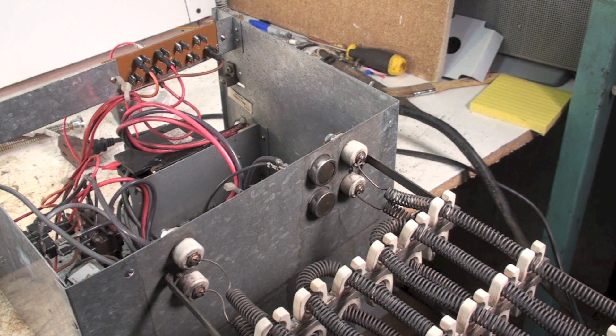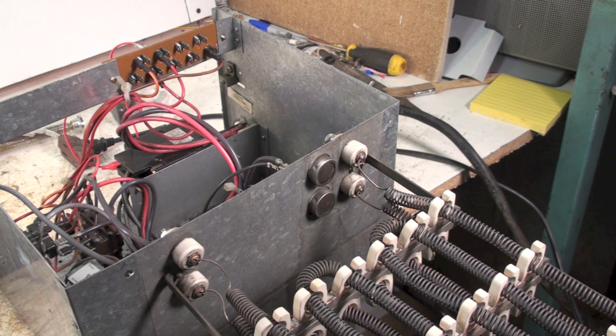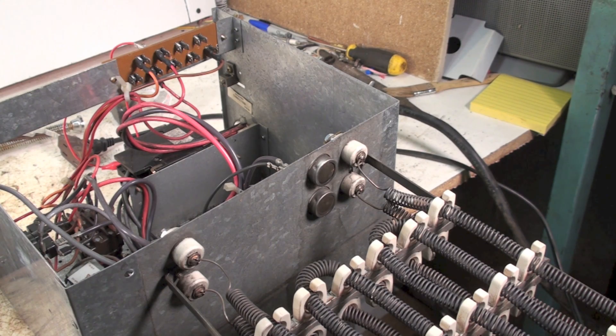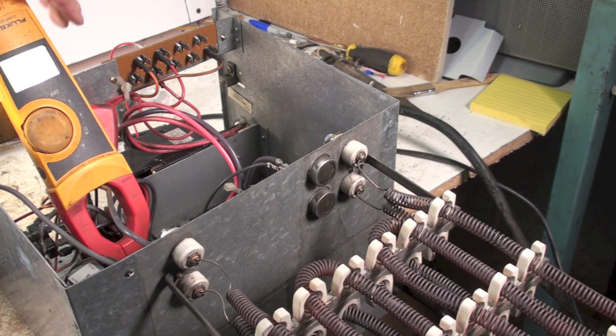Okay, this one's about the limit switches which are right there. Pretty soon these elements are going to come on, and as they come on they're going to overheat. I'll show you the amp draw there.